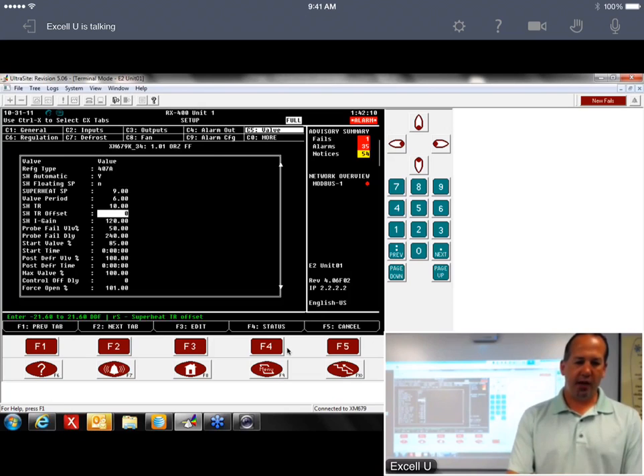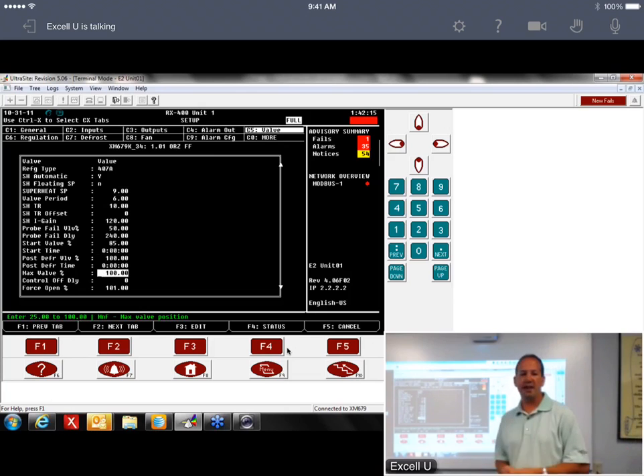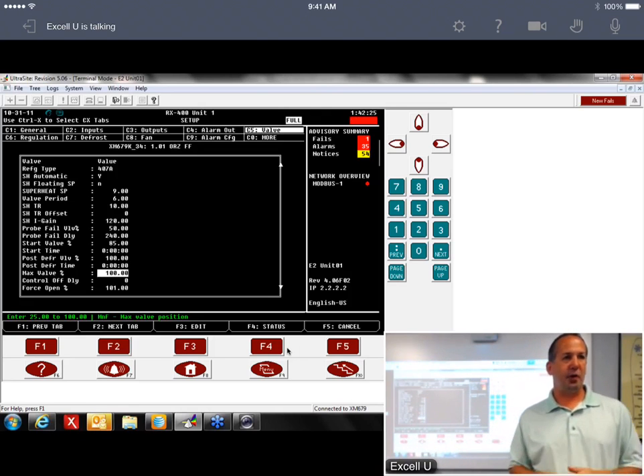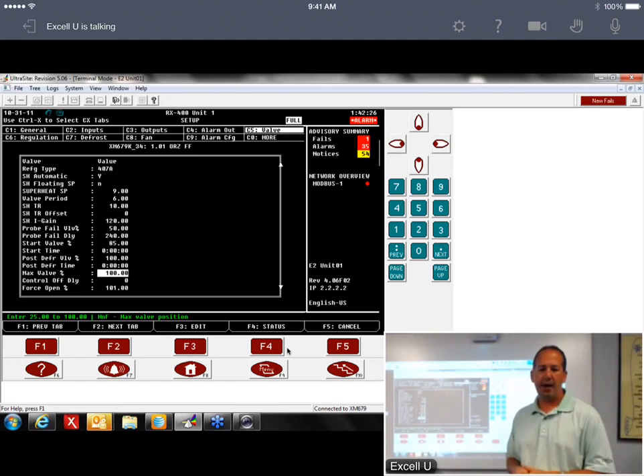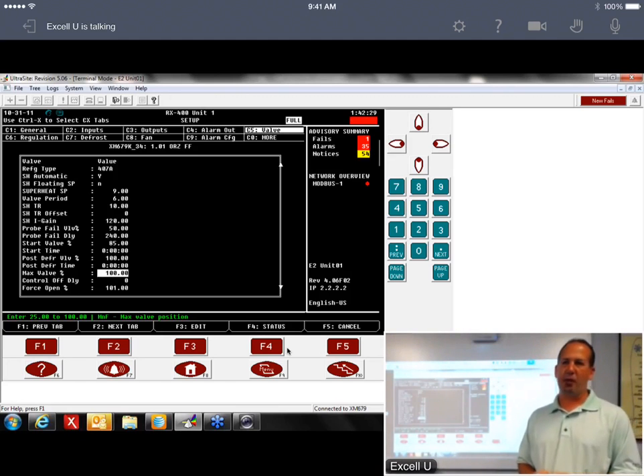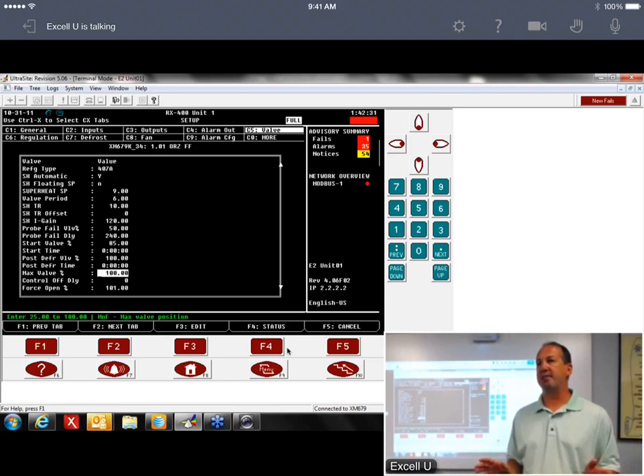Another parameter that we talked about earlier, the max valve percentage. It's in this valve tab. Again, we're in the XM device in the setup C5 valve tab. Max valve percentage resides right there. So if your valve's oversized, I would even say you could probably just about start up every one of them at 80% and be fine.